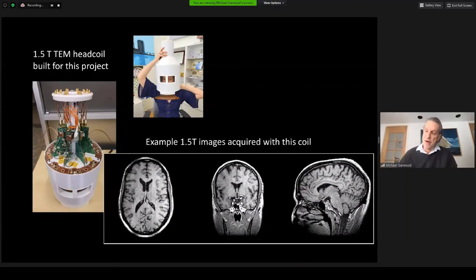Finally, we come to the RF coil that has been built for this system. It's based on Tommy Vaughan's TEM design. It's an 8-element TEM coil with integrated TR switches and preamps. It can operate in a circular polarized mode or in parallel transmit mode with up to 8 separate transmitter elements. Example 1.5-Tesla images acquired with this coil when using the 1.5-Tesla whole-body magnet at the CMRR are shown.